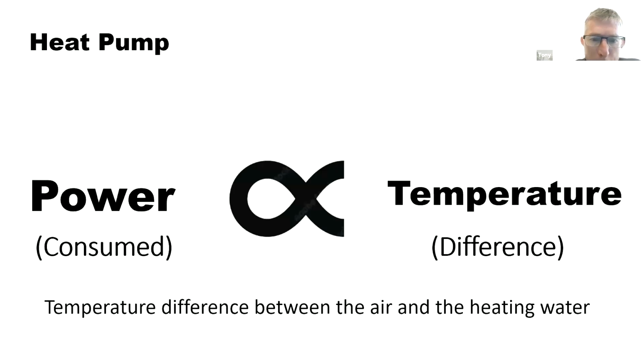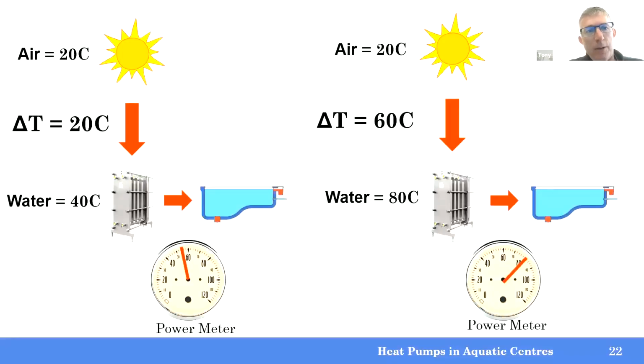Okay, I'm just completely repeating the same slide. This is another slide which I'm trying to explain that with an aquatic centre, when you're using a gas boiler, it's heating water to 80 degrees because that's what gas boilers do. And so a lot of engineers, or some engineers, may think that the best thing to do is to build a heat pump that's going to give you 80-degree water, and then everything else is just the same. But what I'm trying to show here is that if, for example, you use water at 40 degrees to heat the pool, you're only making a temperature difference of 20 rather than 60, and your power is basically triple what it would be if you tried to heat the water to 80 degrees.